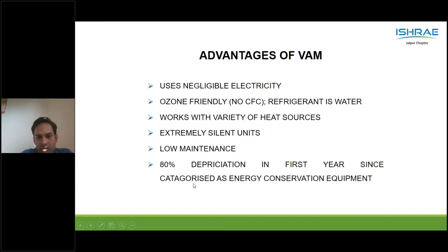Let me briefly talk about the heat sources. The steam that we use is 3.5 to 9 bars in a double effect VAM and 0.4 to 1.5 in single effect vapor absorption machines. Low pressure vapors: earlier in polyester plants, low pressure vapors were produced and exhausted directly into the condenser. Those vapors are 0.05 to 0.4, which is very low, and can easily be used in vapor absorption machines. Hot water at 85 to 140 or 180 degrees Celsius comes from the process.